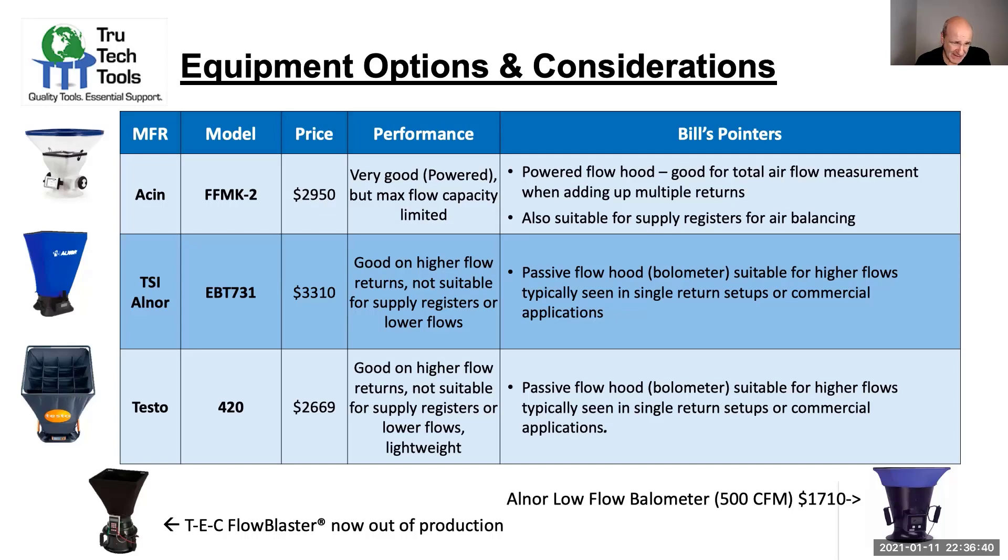The TSI Alnor EBT731 is good for higher flow rates, up to about 2500 CFM, but it's not suitable for lower flow rates. This is a passive flow hood, and it's suitable for higher flows, but it has the impact of insertion loss and accuracy issues, and the way it aligns on a register can sometimes throw off its ability to make a correct reading across many different kinds of residential applications. It's probably best for commercial use.